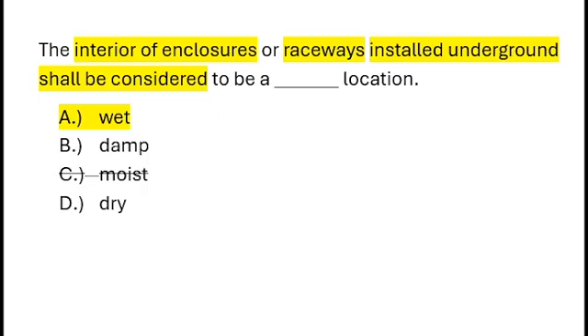Did you guess that right? Let me know in the comments. So why does the NEC classify this as a wet location? Moisture can enter raceways due to condensation or groundwater, and the conductors themselves must be rated for wet locations to prevent insulation breakdown. Proper sealing and drainage are critical to avoid corrosion and potential electrical hazards from insulation failure. If you like this content, be sure to like, comment, and subscribe, and look out for another episode coming out soon.